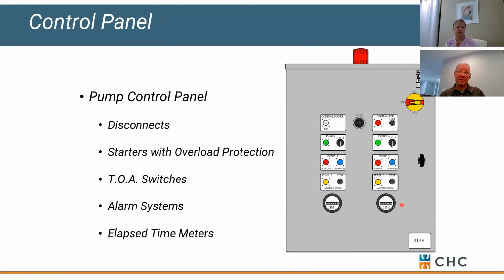A standard control panel is very simple. There's protection in there, typically hour meters to let you know that your alternator is working, and both pumps should have similar hours. The one thing that might be a little unique is a test-off-auto selector switch. Test is simply a spring-loaded hand selector. So the pump will run as long as you're holding the selector switch, but once you let go, it's going to spring back to off. We don't want somebody to let the pump run and then go to lunch and ultimately burn up a pump. So it'll run for you, but once you let go, it's going to snap back into the off position.